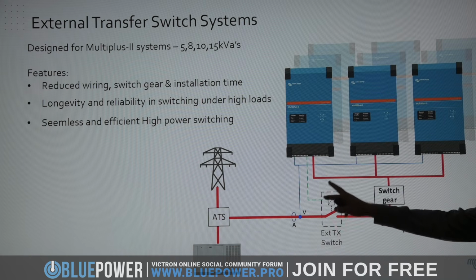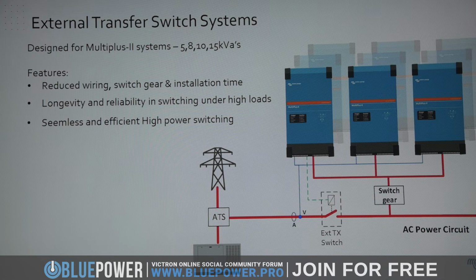So there's the external transfer switch. I've been to a couple of switchboard manufacturers and given them a spec. They've designed the box and given me a quote on these boxes. I've been to 2 in Cape Town. It doesn't look that expensive, and it's a switchboard manufacturer, which is basically what you want. You say, I want a 100 amp transfer switch, and the white box gets delivered. You don't have to go build it yourself, because that's the big thing.